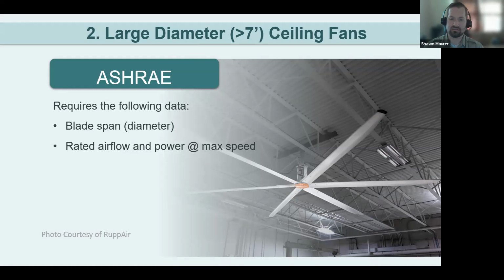ASHRAE also includes some requirements for ceiling fans of large diameter. So we're looking at fans that are greater than 7 foot blade span here. They have requirements for rated airflow and power at maximum speed. It's a new requirement for large fans. Part of it is to raise awareness for how much power these can consume and how efficient they are.